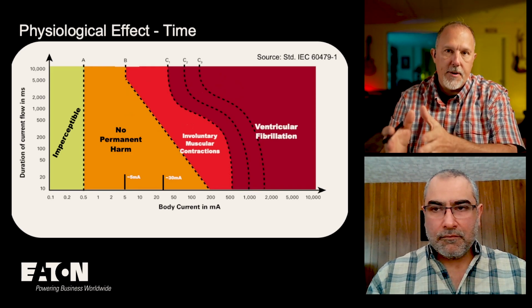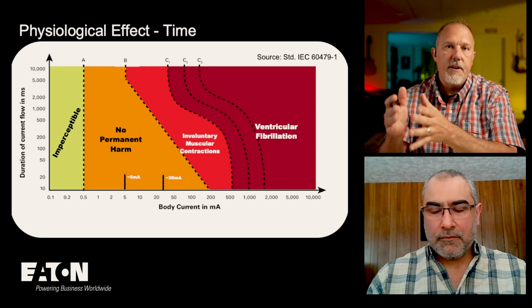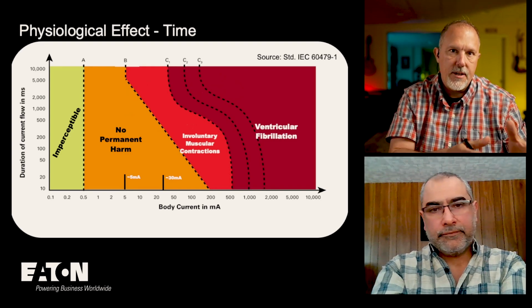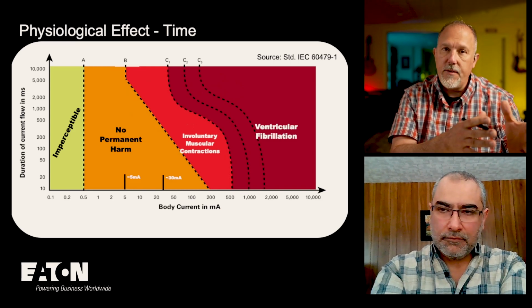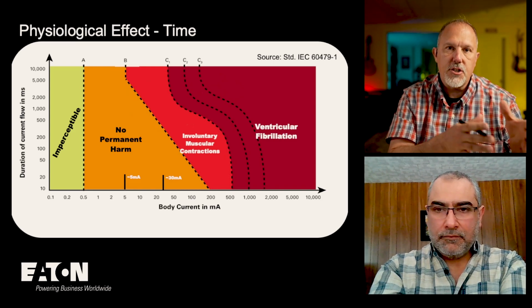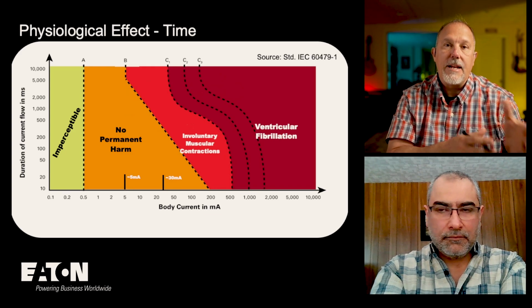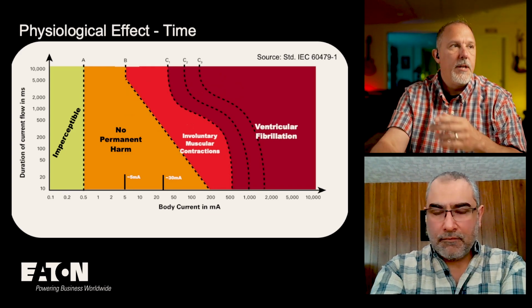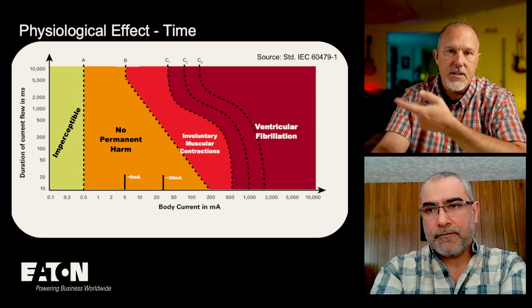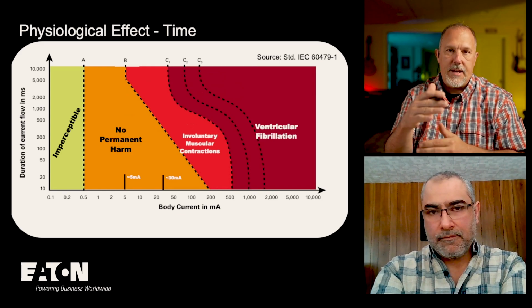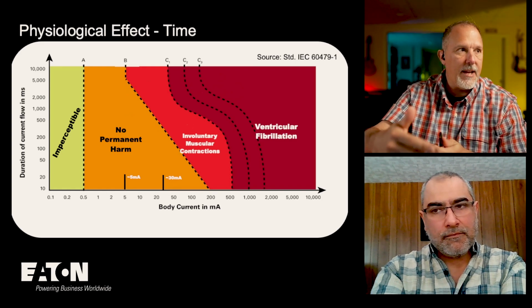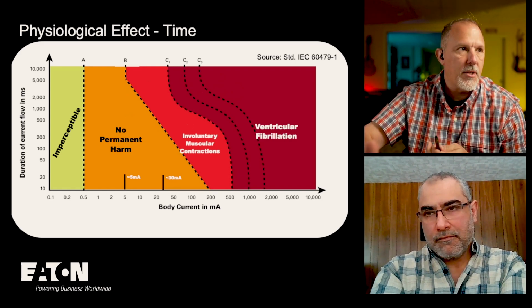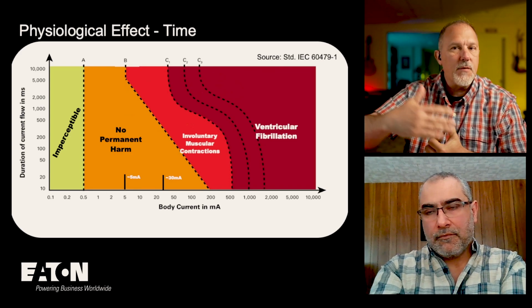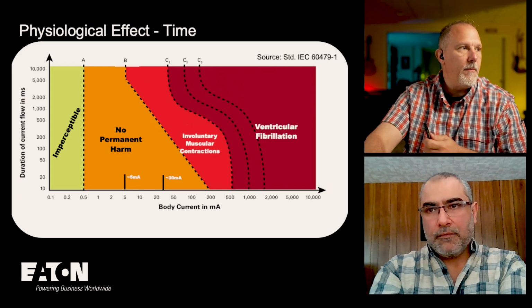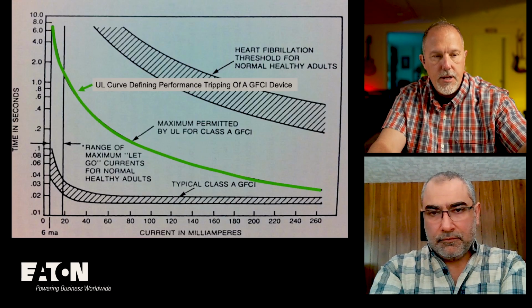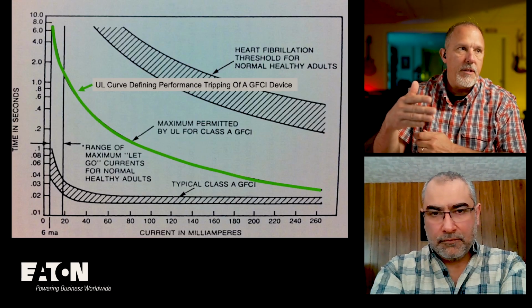So they're worried about ventricular fibrillation. And then the U.S. and the Americas markets, where we follow 70E and the National Electrical Code, they worry about the let go thresholds, which is that 4 to 6 milliamps. So this, I really like this slide because it gives you that perspective. A lot of people don't understand that the body can take, say, 50 milliamps or 100 milliamps, but just for a shorter period of time, which gets you directly, to your point, into the curves for the GFCI.